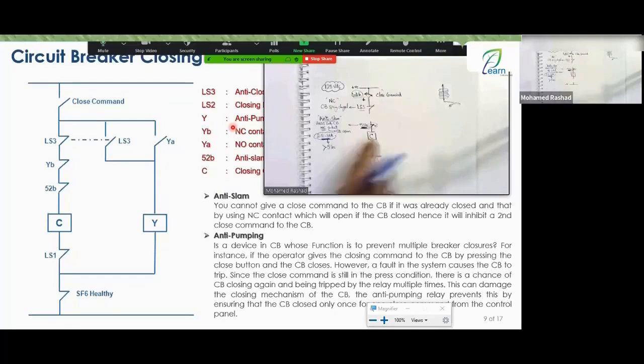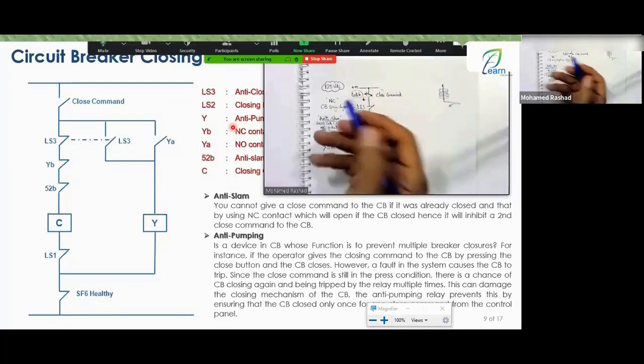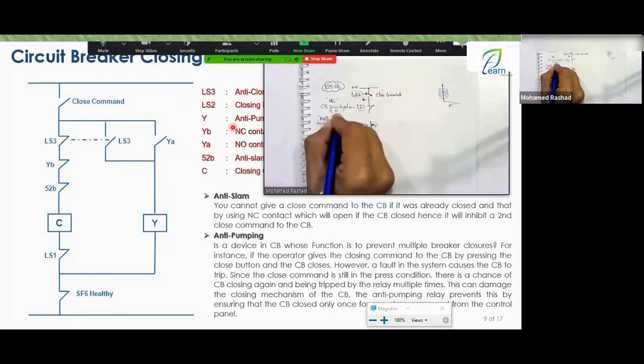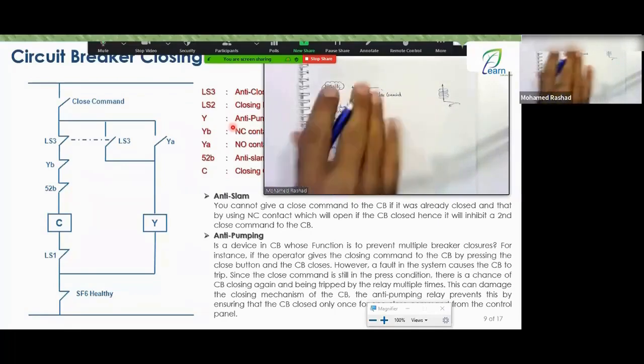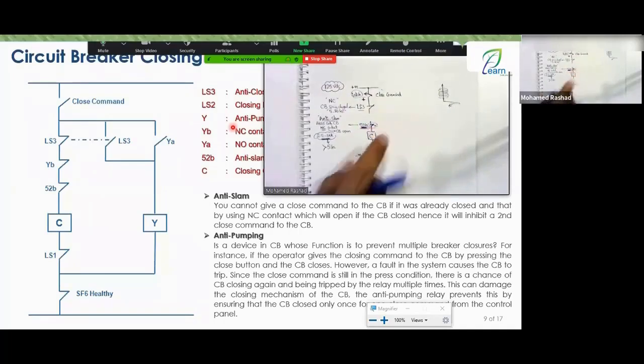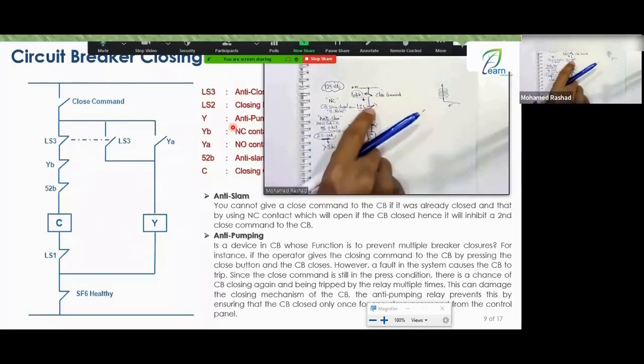So this opened, meaning no DC will reach here until after the spring charging time, which is about 5 to 10 seconds. This contact returns to close again because the spring is charged, and this remains open because the breaker is already closed. The breaker opens, this returns to close, and this closes. A command comes here to close, so the breaker closes. As soon as the breaker closes, a fault will occur. The fault is present, so the breaker will open again. This will close, but that hasn't closed yet because the spring is still charging, so it continues to charge. Once it finishes, this closes and that closes, the DC reaches and the breaker closes. The fault is still present, so the breaker opens.